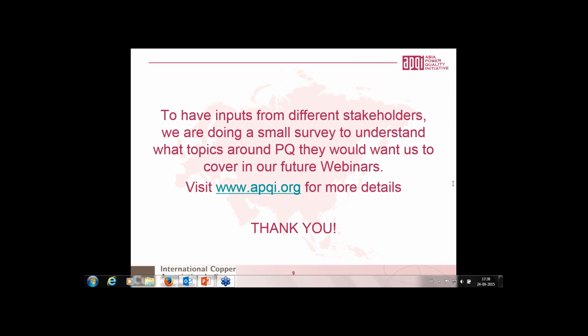I would just like to add to what you had said. Especially for the meters which we have installed, they also have this facility of upstream or downstream detection. Our experience is that sometimes the meter shows it is upstream, but we do not get any information with respect to the tripping in the grid, because the grid is a vast network with many players. So if any tripping occurs at a line which is, say, 200 miles away, there is some voltage dip. Sometimes, even though the meter shows upstream, it is difficult for us to exactly pinpoint what that was.